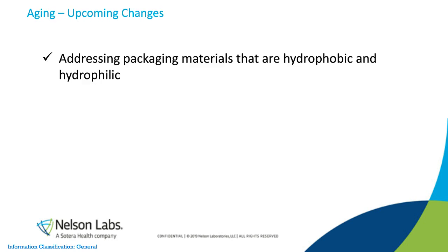The ASTM F1980 standard that governs accelerated aging is up for revision. They are looking at the effects of moisture on materials. Some materials will absorb moisture and some do not. Some failures after accelerated aging may not be real, especially when those failures are not duplicated after real-time aging. This might lead to some recommendations on humidity levels or some other things there. We're just going to have to wait and see. All right, Wendy, it's back to you to finish things up.